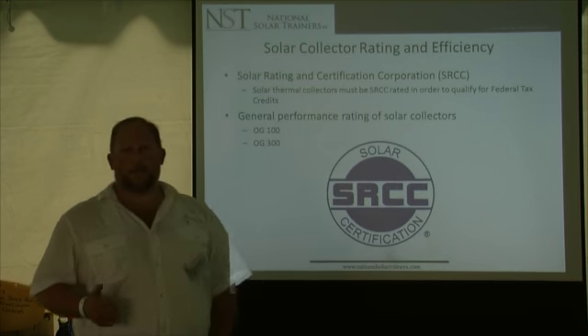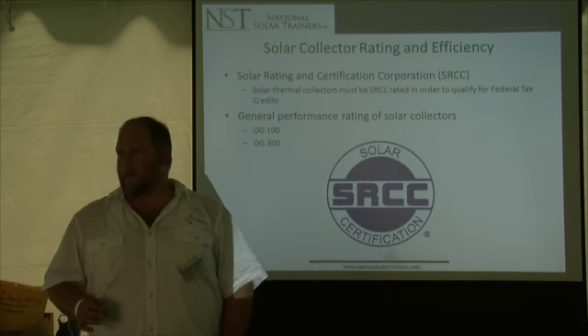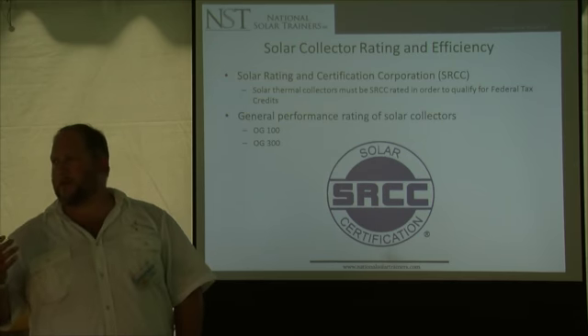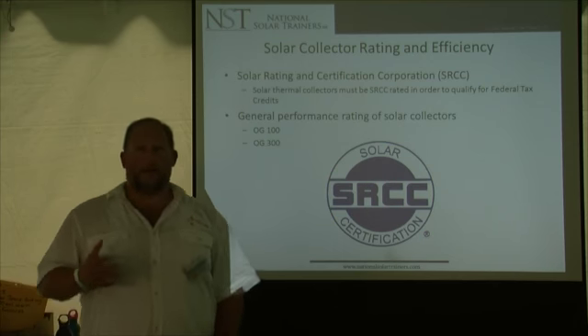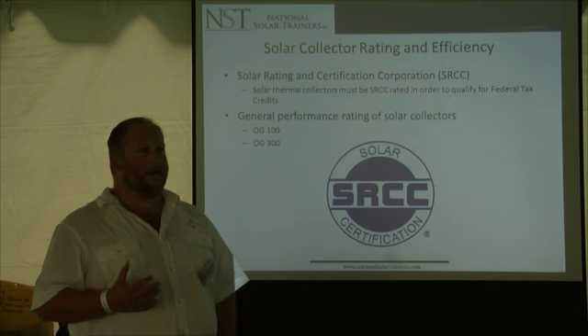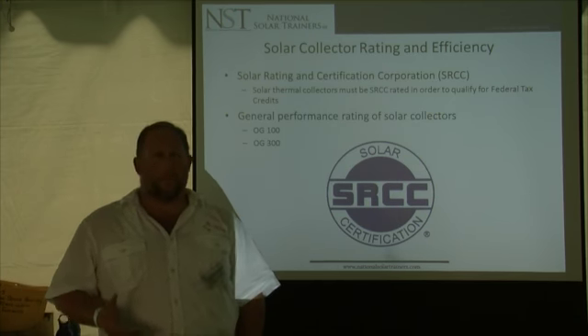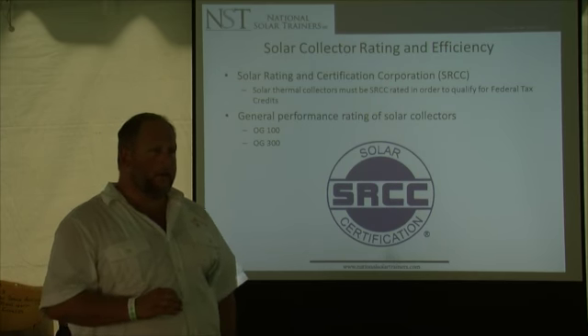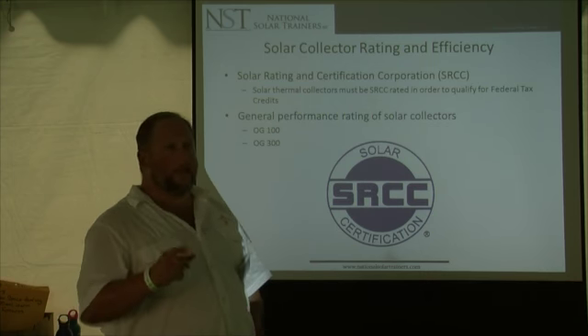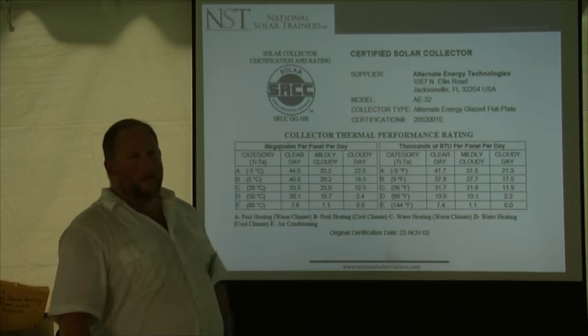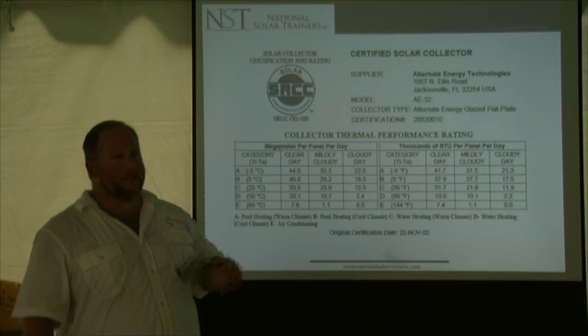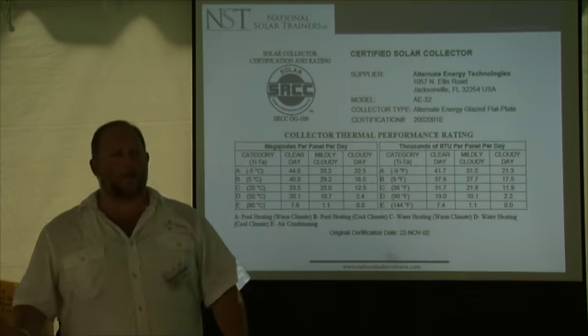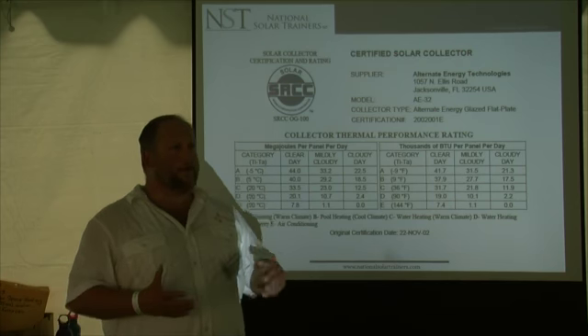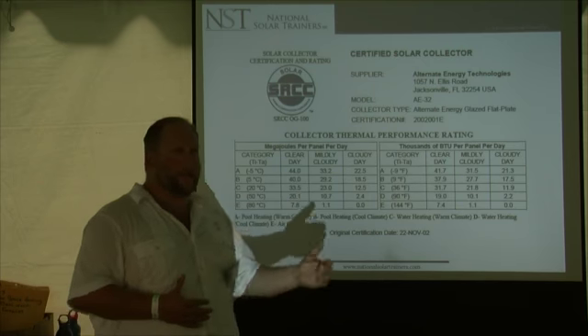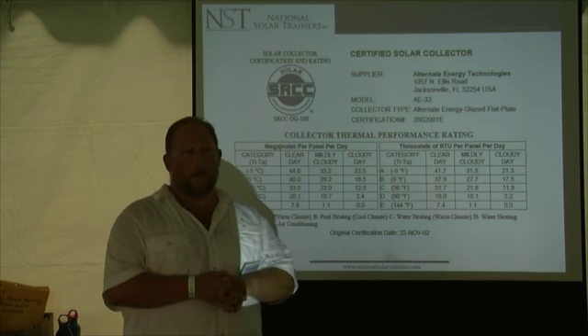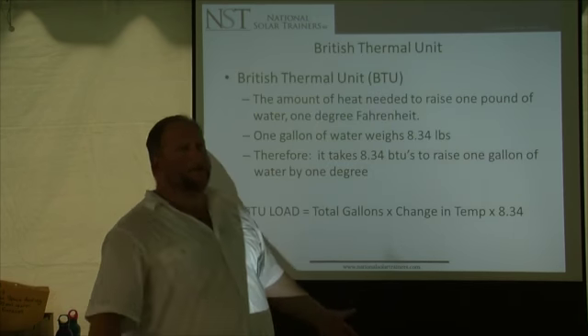The SRCC is the certification for all thermal collectors. If you're going to search out collectors to purchase, they have to be SRCC certified to get the tax credits, which are significant. SRCC is sort of like the UL - if you're going to buy collectors, they have to have the SRCC sticker, and they give you a chart of how much energy you should expect. Manufacturers don't make up the numbers; the production numbers they give you have to come from SRCC, an independent testing company. It basically allows you to compare apples to apples.